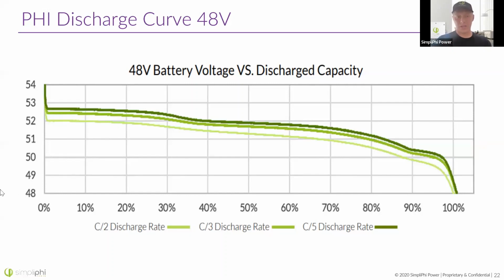For example, let's say you're at 51.5 volts and you've got a C/2 load, that could really be anywhere from 60% to 30% state of charge. So you not only have to know how much load, but you also have to have a good understanding of this chart. It's a whole mess. You need a battery monitor instead. It's going to measure the current going in and out of the battery at all times and calculate that state of charge for you.